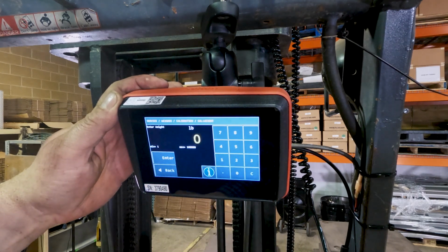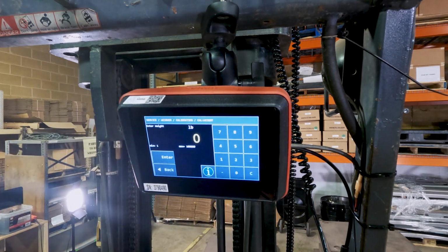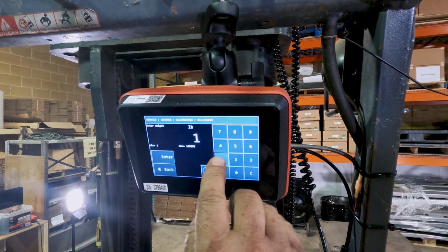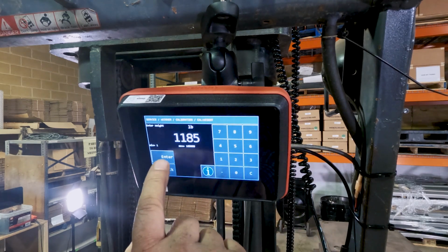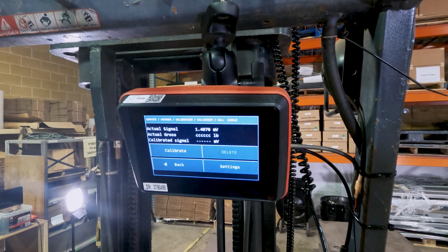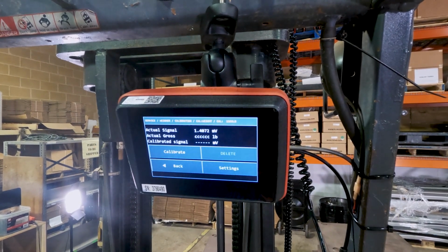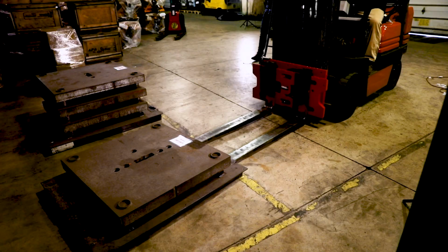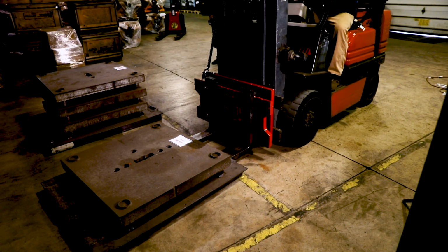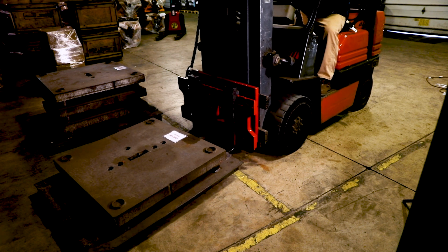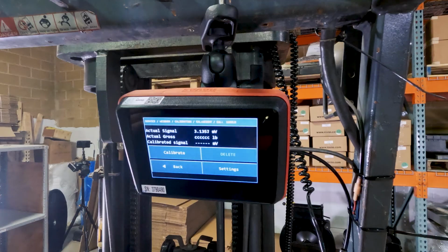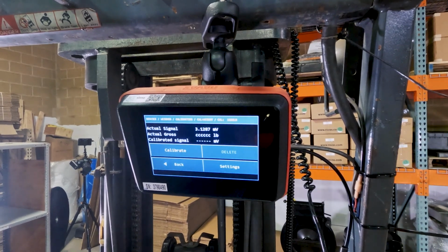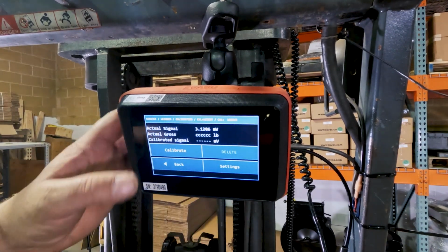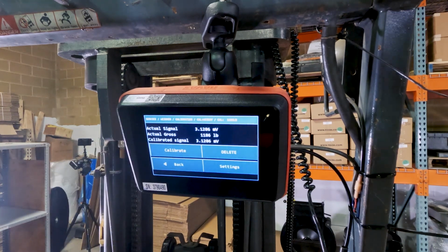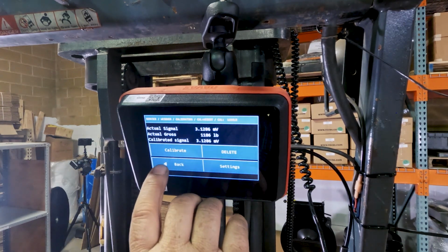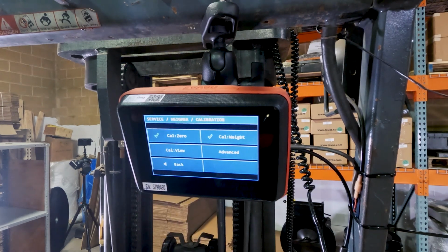We will now hit Cal weight. We will enter the weight of the object that we are picking up. We will press enter. That is now our reference weight. We will pick up the weight. We will let the weight stabilize. As you can see in the millivolts staying constant, we will hit calibrate. Our first weight is now calibrated. We will hit the back button and we will set our object down.